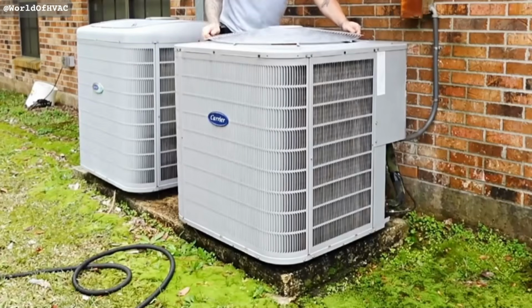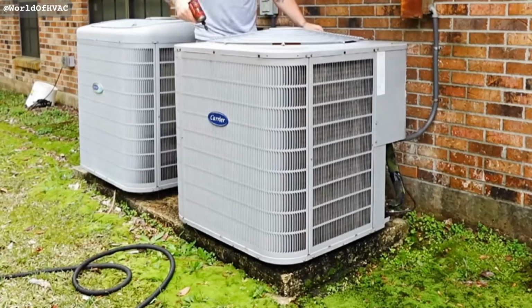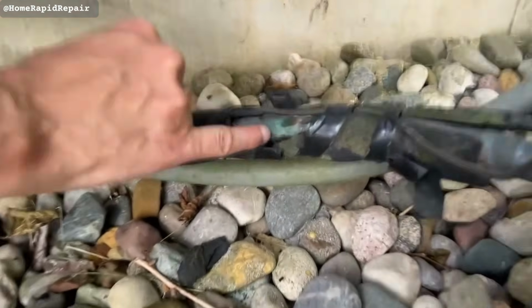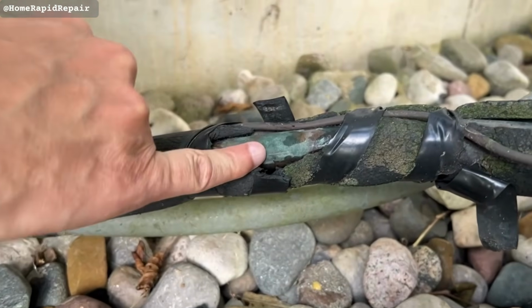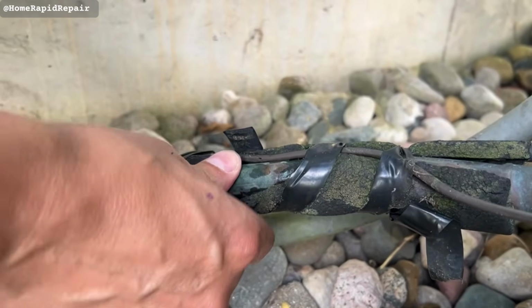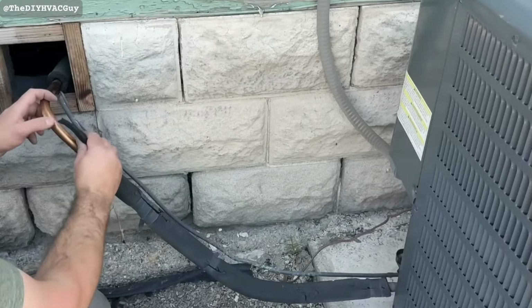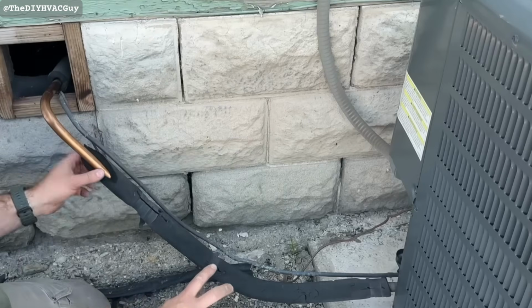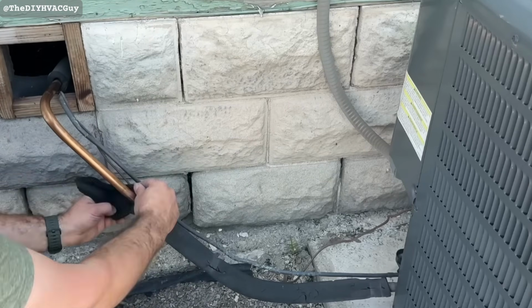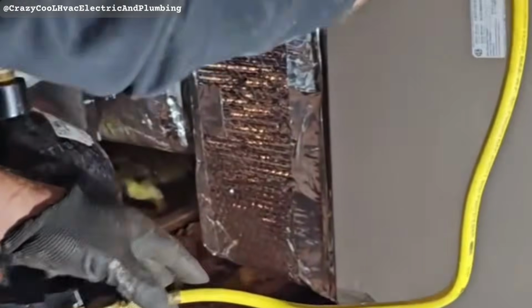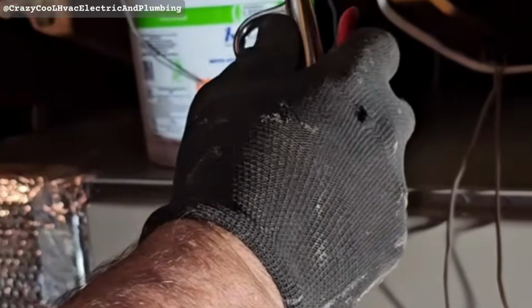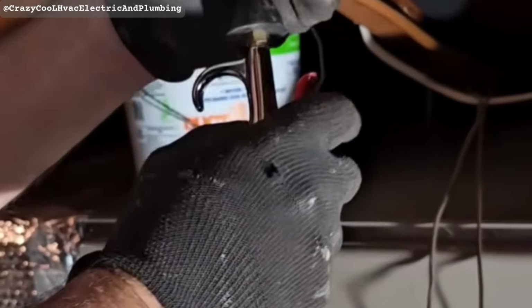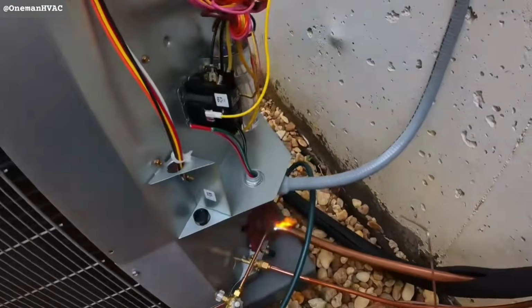Second, a soft start kit on the outdoor unit. Newer than a hard start kit and gentler on the compressor. Soft start ramps the motor up over a half second instead of slamming it from 0 to full speed. Compressor inrush current drops by about 40 to 60%. Less strain on every start, every day for the life of the system. About $250 to $400 installed.